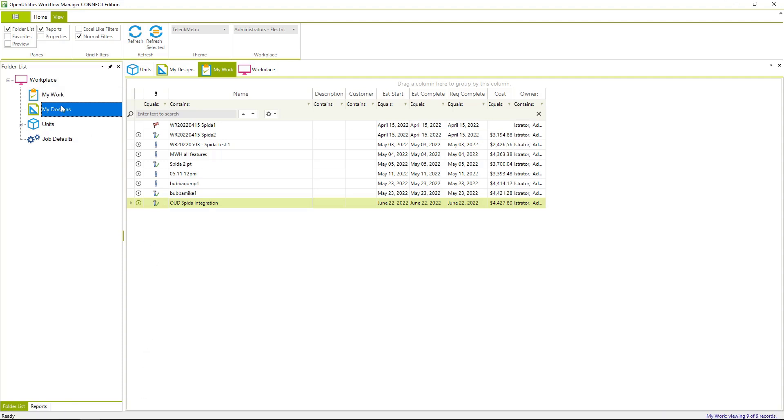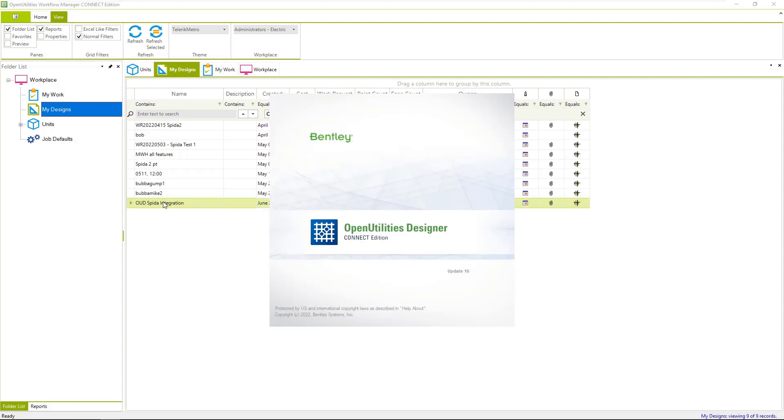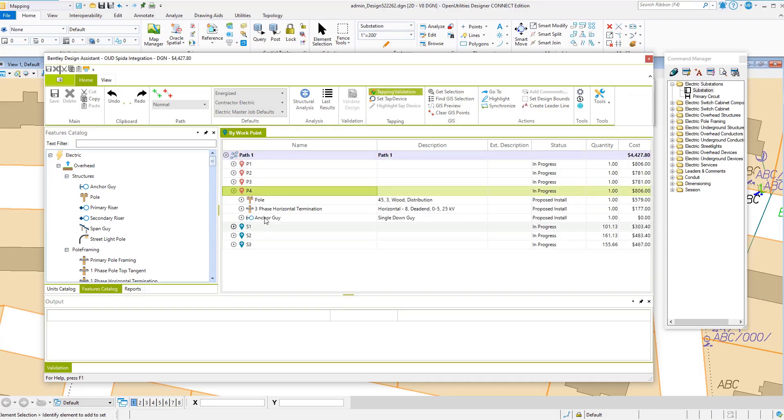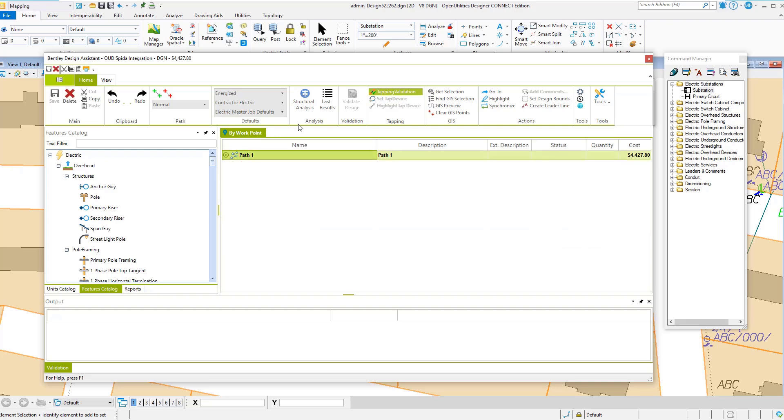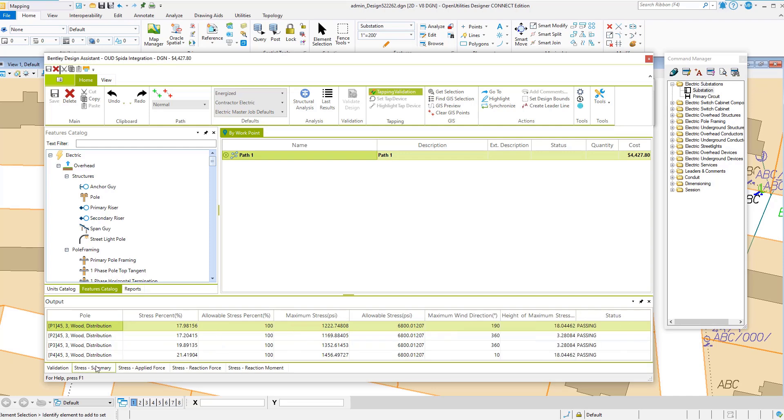So we can go to our design, open that up. We have our design with the anchor guy, and we can view our last results. And the main thing is when we come to the stress summary: pole 4 is at 21%, and it's passing.